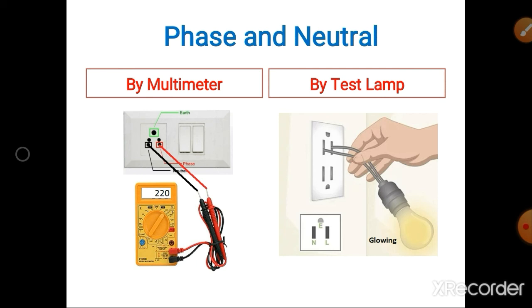Look at this diagram. We are checking whether the supply is coming from the main switchboard to the plug or not. The phase and neutral points of the 5-pin socket are connected to the multimeter: the red pin to the phase point, and the black pin to the neutral. After switching on the single way switch, the multimeter shows 220 volts, meaning we are getting supply at that 5-pin socket.